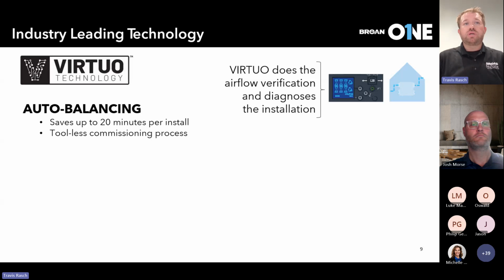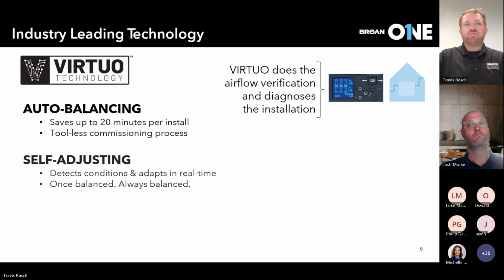So this is a completely toolless commissioning process. No gauges, no damper adjustments, no motor speed adjustments, etc. You can keep the door on as is, simply interact with that LCD screen and do your full commissioning, and the unit will stay balanced during this time.